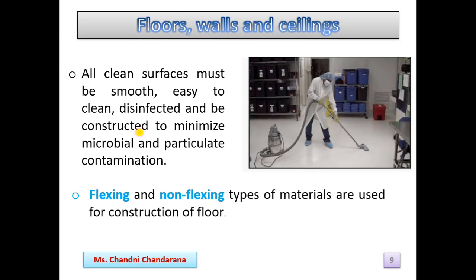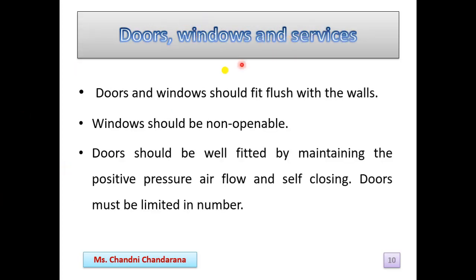This is how the aseptic area or production area for sterile products should be. Now, for doors, windows, and services: doors and windows should be flush-fitted with the walls. Windows should be non-openable. Doors should be well-fitted, maintaining pressure airflow, self-closing, and limited in number. All pipes passing through the walls and rooms should be effectively sealed and flush-fitting and easily cleaned.